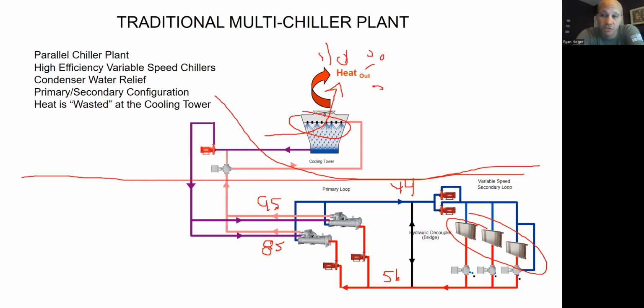So I do have to pay for some extra water on this kind of system, but it's really efficient. Electrically speaking, it's way more efficient than an air-cooled chiller would be. So you're trading off the cost of electrical energy for the cost of water energy. And depending on where you live and how expensive water is, one or the other might be a better deal. And then if you get to very large buildings, high rises, like 100 stories and bigger, you're not going to have the space to put air-cooled chillers. You're going to have to do cooling towers. So at that point, the cost of water is irrelevant because you can't do anything other than this.